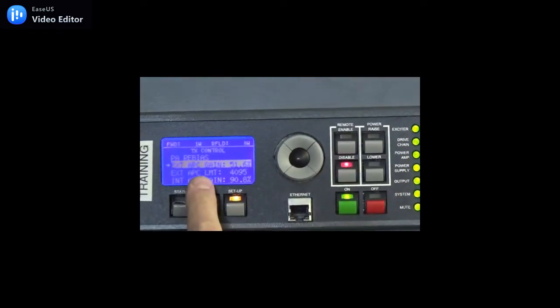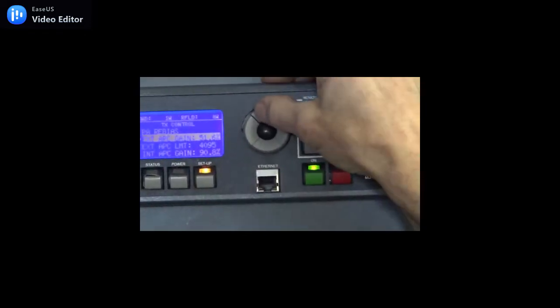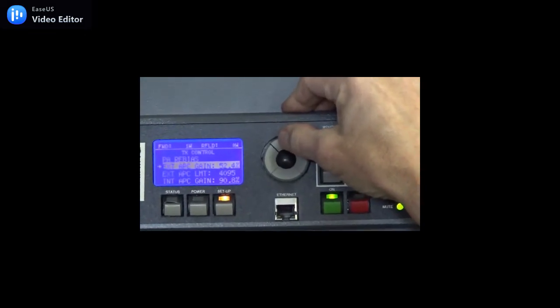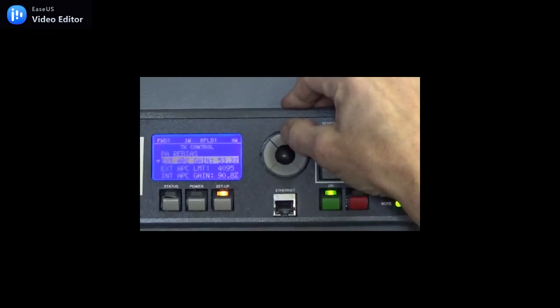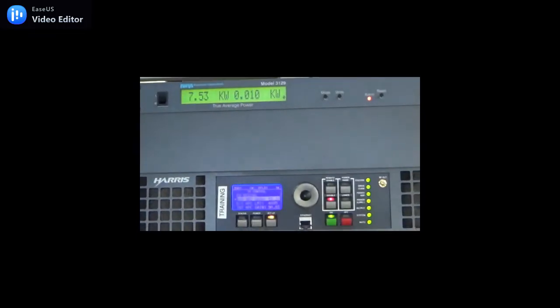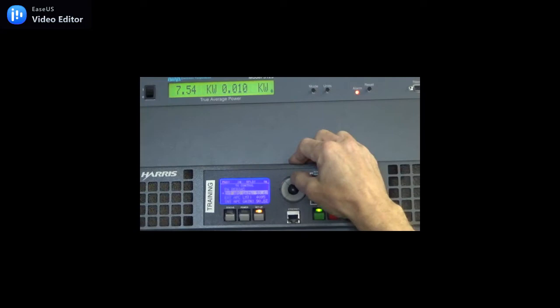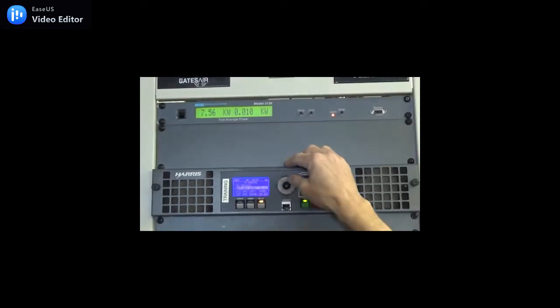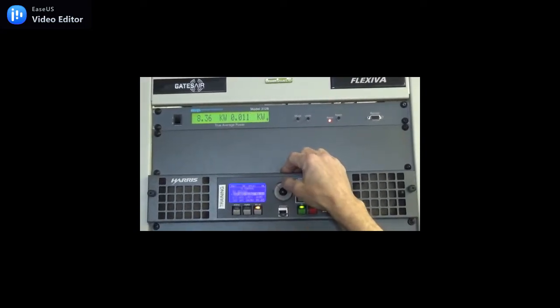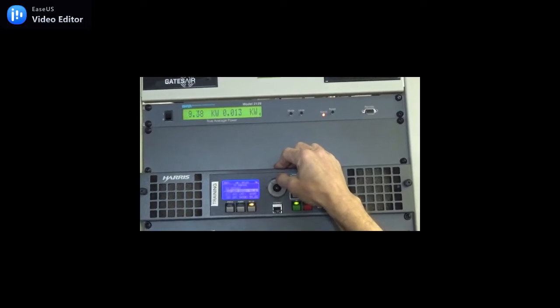So we're going to do that by going into the external APC gain. And we're going to start increasing that gain. And you're going to watch this external meter or whatever meter you have. And we're going to wait until we get to the TPO we set down in the power block. And in my case, it's going to be 9,900 watts.